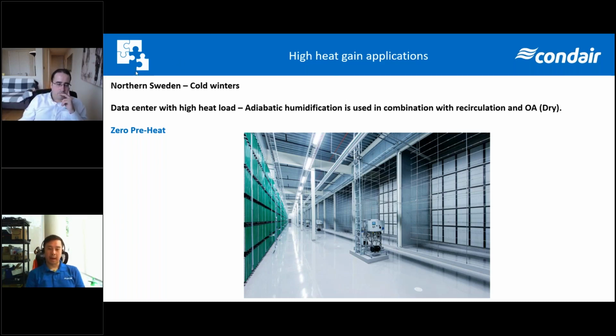So in this case, because we were atomizing the water, we had to supply a fairly large water treatment system as well. And if you recall, when we spoke about this earlier, what we're seeing now is a focus on water consumption. Right off the bat, you're penalized by going through an RO system. You're going to have 30 to 40% of that water going into the RO system sent directly to drain, just because that's how RO systems work in terms of pulling minerals out. We also have some inefficiencies on the atomizing system as well. So the water consumption on these types of systems where we're spraying water is significantly higher in most cases than a more traditional direct evaporative system or media system, which is one of the reasons I think that we are seeing a shift back towards those types of systems, because water consumption is being looked at a lot closer now.